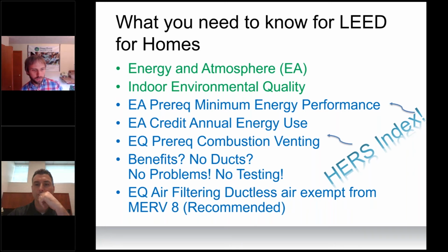The other good news is if you're going with the ductless systems, no ducts, you don't have to do any of the duct testing, which can lead to all sorts of problems for LEED. We see it all the time in the field. So no ducts, no problems, no testing. And then the last one, very interestingly, is these ductless systems are exempt from the MERV 8 requirement for filters in the EQ air filtering credit. And so you can use the one that it comes with, which I believe, and Mike, correct me if I'm wrong, is lower than MERV 8.